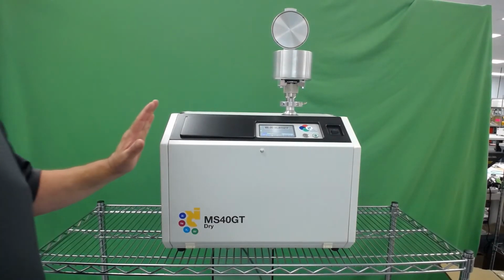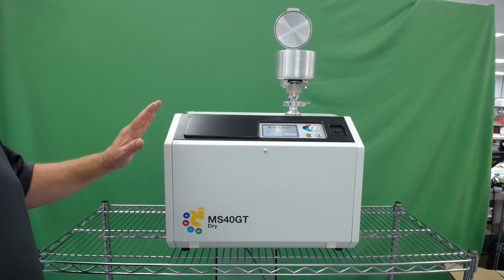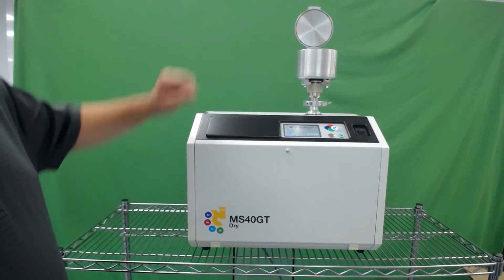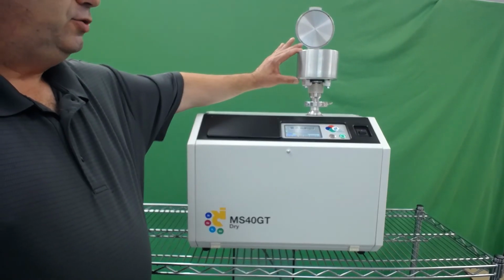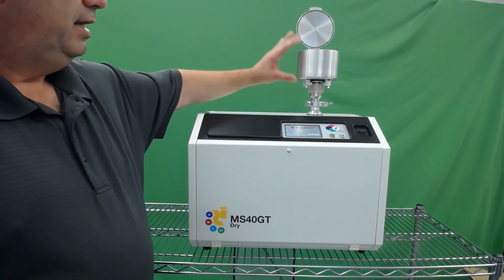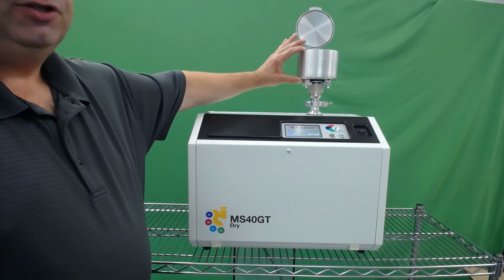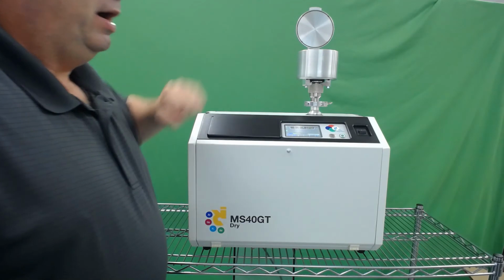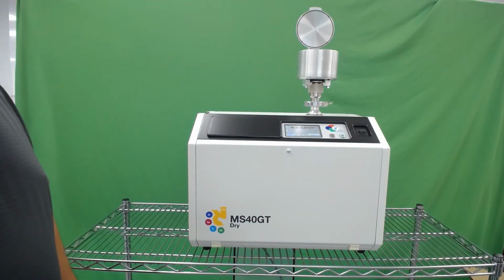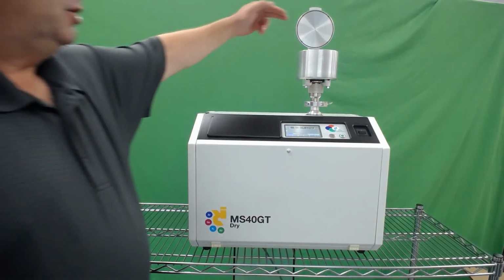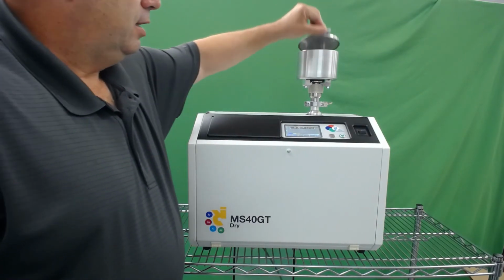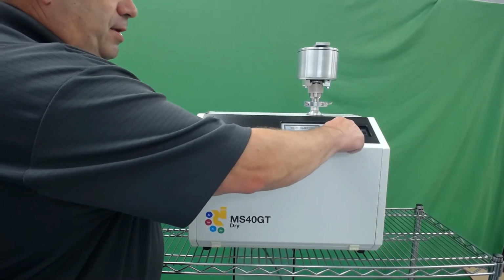The MS-40GT series helium leak detector can be equipped with a number of options. Installed on the top of the unit is one of our custom fabricated test cups. It's approximately 3.5 inches deep and 4 inches wide. This is ideal for testing hermetically sealed parts such as integrated circuit chips. The customer will place the products into the chamber, close the lid, and press the start button to initiate the cycle.